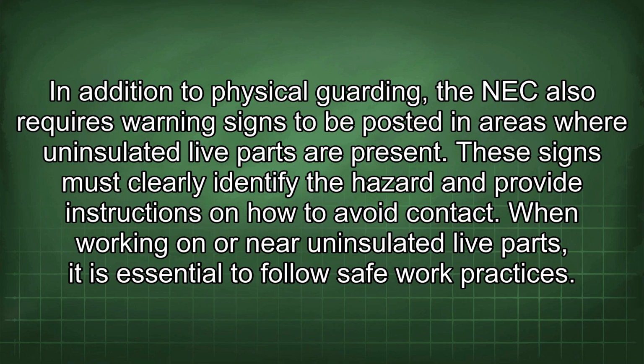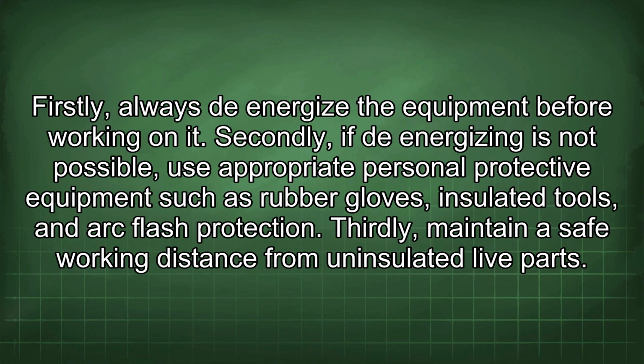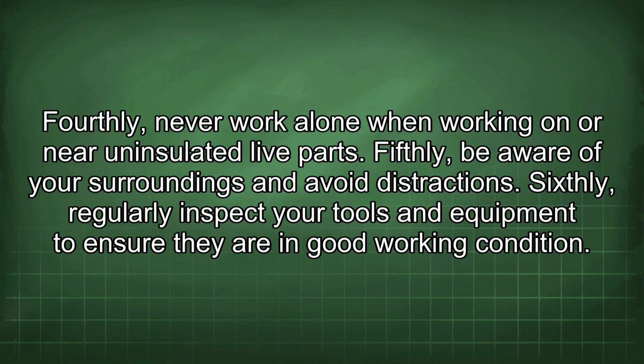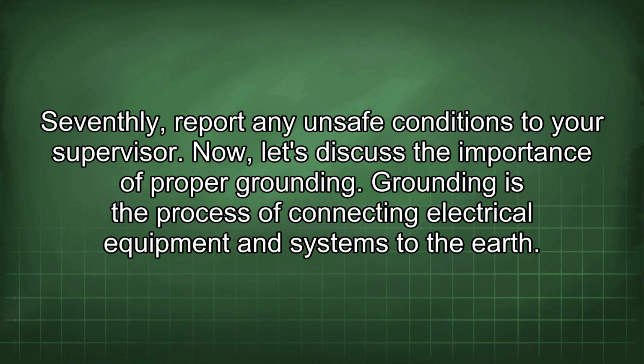When working on or near uninsulated live parts, it is essential to follow safe work practices. Firstly, always de-energize the equipment before working on it. Secondly, if de-energizing is not possible, use appropriate personal protective equipment such as rubber gloves, insulated tools, and arc flash protection. Thirdly, maintain a safe working distance from uninsulated live parts. Fourthly, never work alone when working on or near uninsulated live parts. Fifthly, be aware of your surroundings and avoid distractions. Sixthly, regularly inspect your tools and equipment to ensure they are in good working condition. Seventhly, report any unsafe conditions to your supervisor.